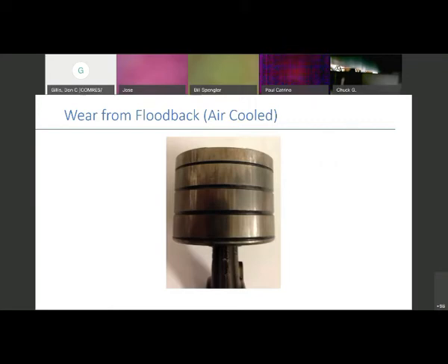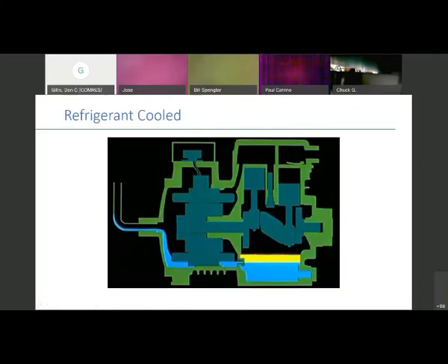It's consistently, almost exactly, fairly close anyway, what this looks like consistently. And what's happened here is this has washed away the Lubrite. This is a cast iron piston. These are oil grooves in this piston, and you can see how this has lost its color there. That's coated in Lubrite, and solvent or POE oil refrigerant acts as a solvent. So this has washed away the lubricity and caused a little friction there, okay?